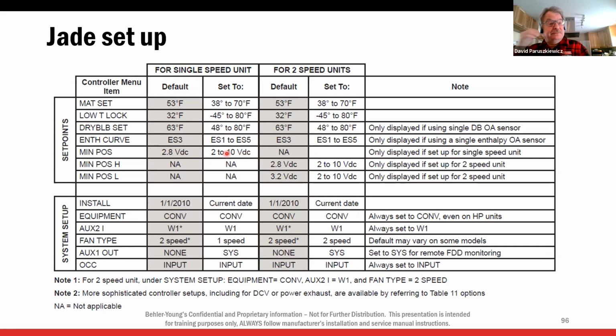And we talked about using a temperature probe to correctly set our mixed air. Now, if I have a 2-speed blower, I'm going to have minimum position high and minimum position low. High is 2.8, low is 3.2. Because again, on low, the damper is going to be further open. A lot of guys leave it at this. It's not correct, but it'll work. Okay, so most of these factory settings will work great. You'll never have to mess with it. But let's go down to system setup.